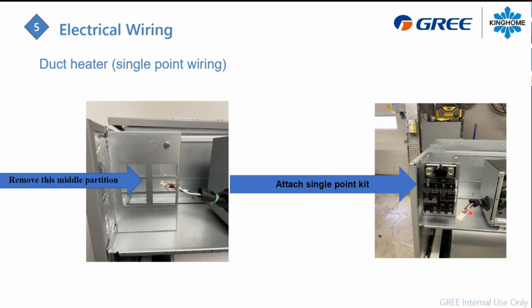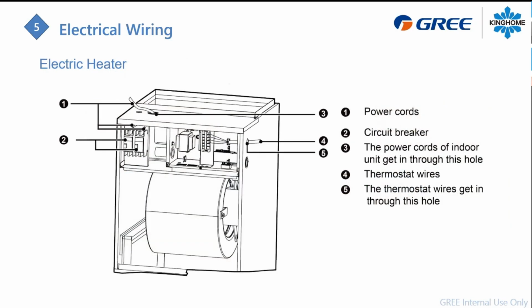So by the white Molex right here, the 240 volt, it's already powered passing through the breaker here. So you don't use anymore the L1, L2 connection right here. So you don't have to. There's already a wire going from the breaker to power up the board and all the stuff for the unit. So when you're using a duct heater, you don't have to use the L1, L2 connection here.